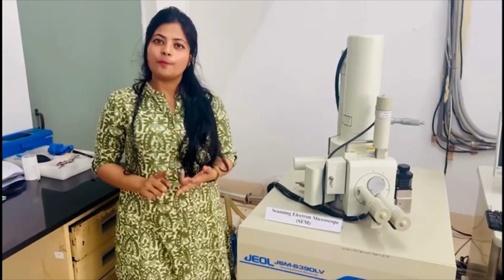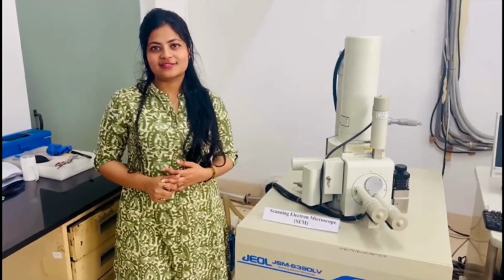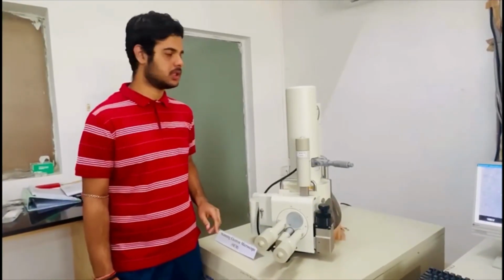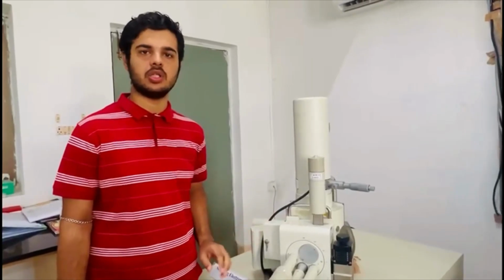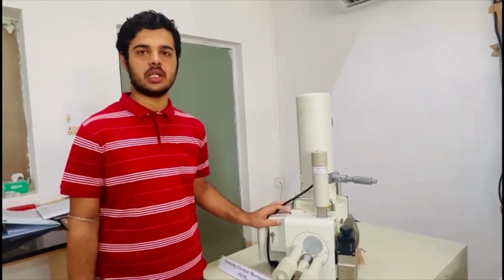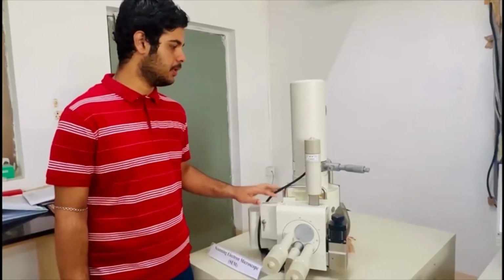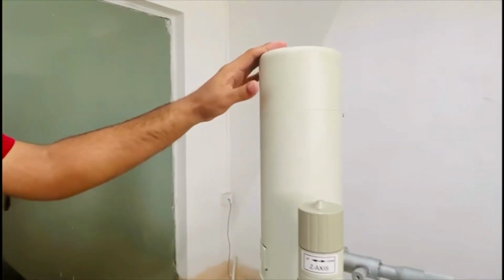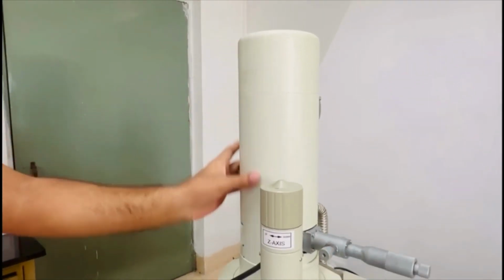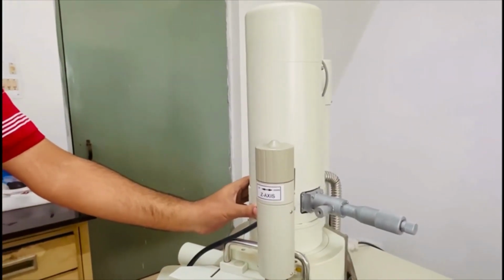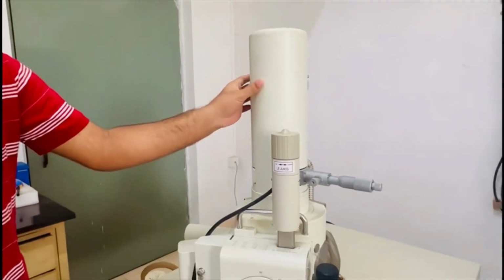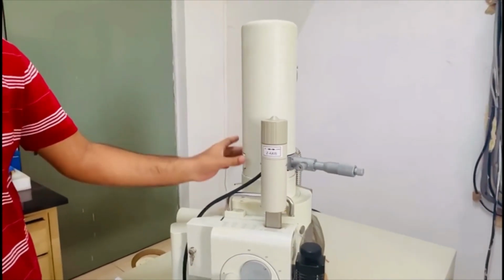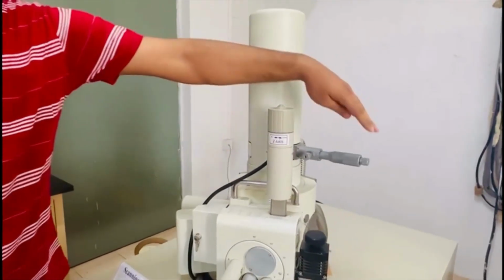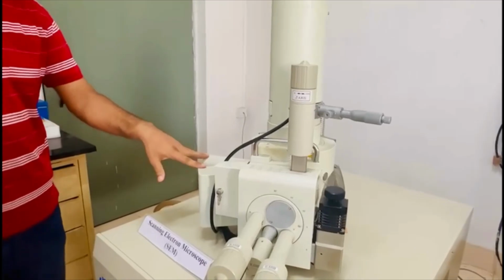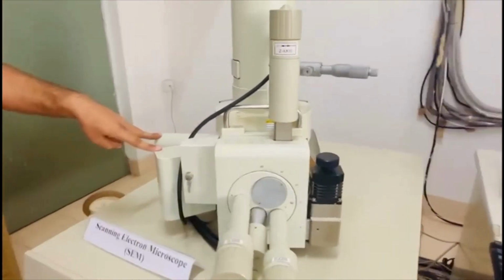The major applications of this instrument are surface morphology, compositional analysis and topographical analysis. Now I am going to tell you about the working principle of this machine. The machine works on the principle of electron interaction with matter and the images are taken from the electrons backscattered from the sample. This part of the machine is the thermal gun from which the electrons are generated, and this is the column from which the electrons travel to the sample. In this part there are various lenses like condenser and scan coils which focus the electrons. This is the aperture and these two are the various parts from which the images are detected.